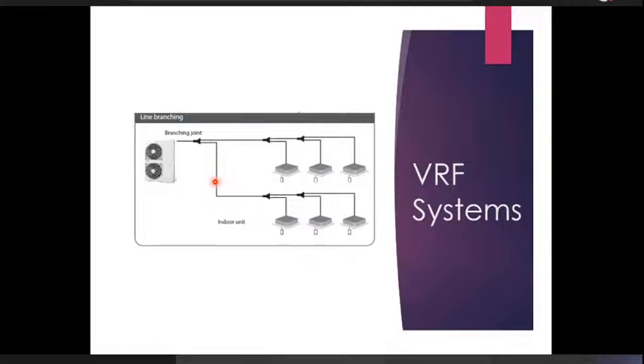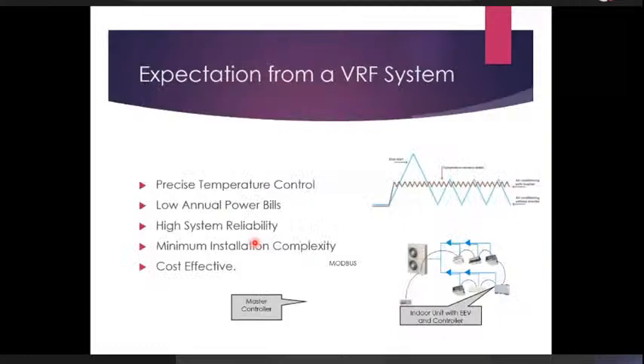Now, what are the expectations we can have from a variable speed system? The first thing is that it is going to lead to a more precise temperature control. If we sit in front of a normal window or a split air conditioner where the compressor goes on and off, particularly on humid days, we can sense the air quality changing. When the compressor goes off, we can feel that there's a bit of humidity and the smell is not fresh anymore. Whereas when it is running, we tend to like the odor and the overall sense of freshness in the air. That is because there is a dehumidification part that is happening all the time.